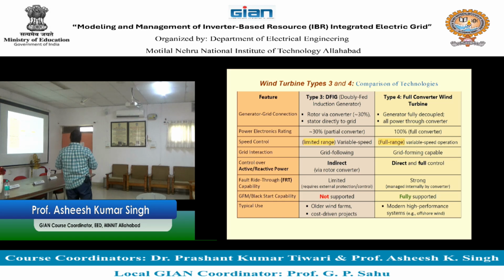Next point is grid interaction. Type 3 has GFL, type 4 has GFM. Control over active and reactive power is again partial in type 3, so this is indirect control, with direct control only on 30% of generation and the remaining indirect. Type 4 has direct and full control on the complete system.